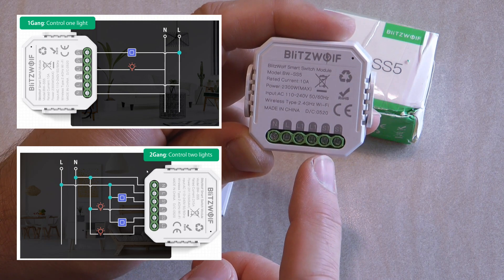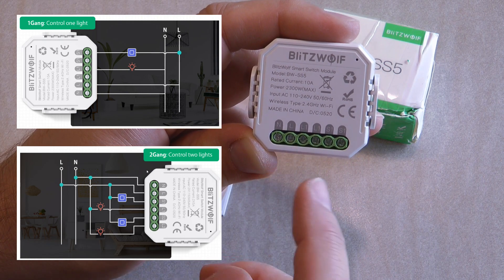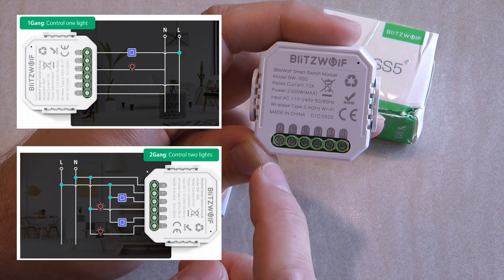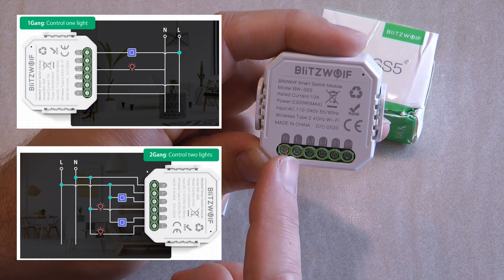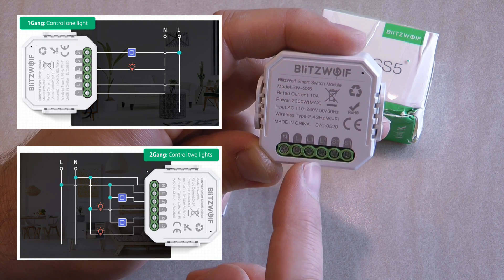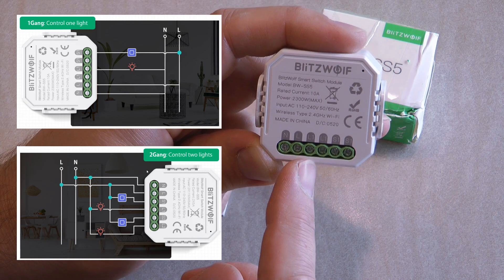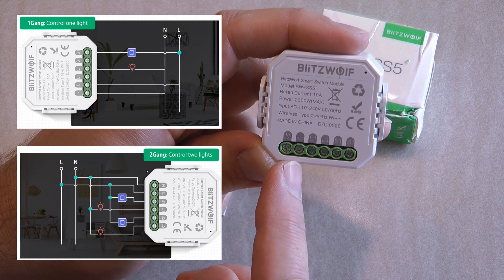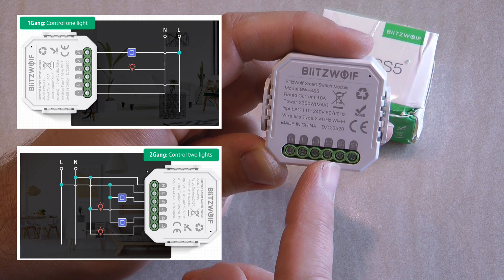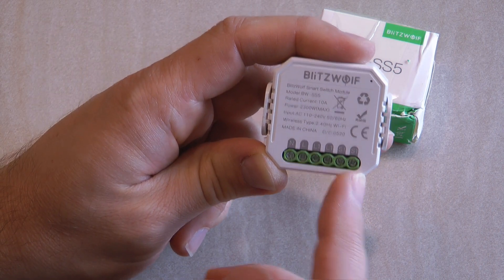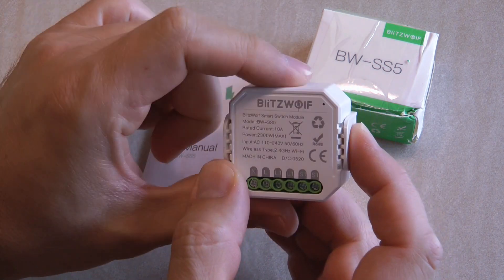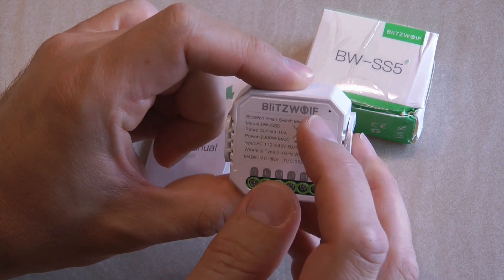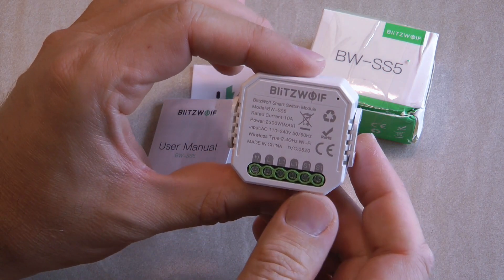You are switching the live mains voltage into the unit. So the neutral gets connected here, the main live gets connected here, these are the lives that go to the lamp you want to control, and the switches are connected between L and S1, or if you have a two gang version between L and S2. There is no other control on this device.